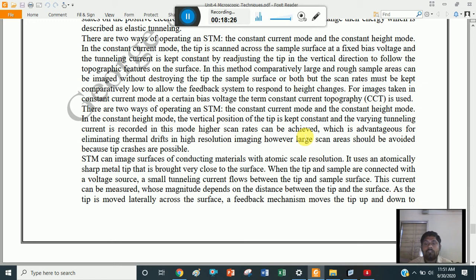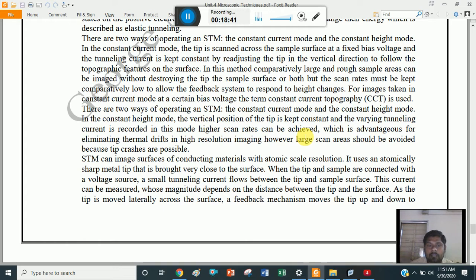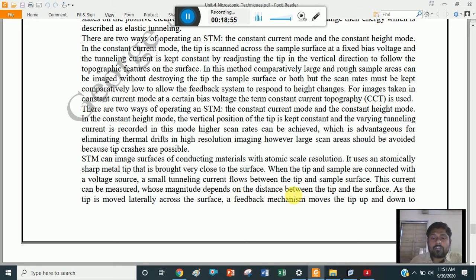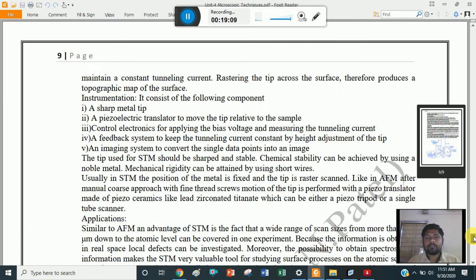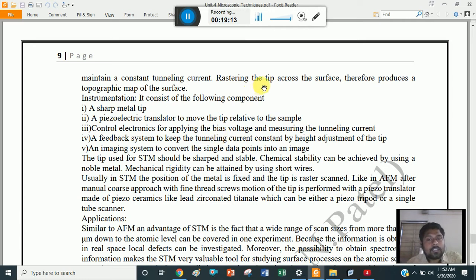When a tip and a sample are connected with a voltage source, a small tunneling current flows between the tip and sample surface. This current can be measured, and its magnitude depends on the distance between the tip and the surface. As the tip is moved laterally across the surface, a feedback mechanism moves the tip up and down to maintain a constant tunneling current, rastering the tip across the surface, thereby producing a topographic map of the surface.